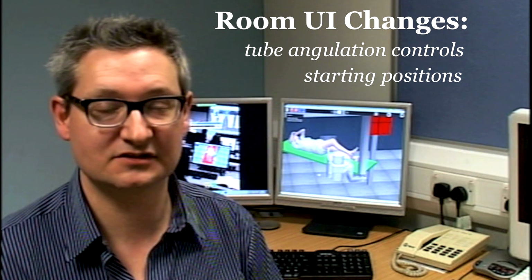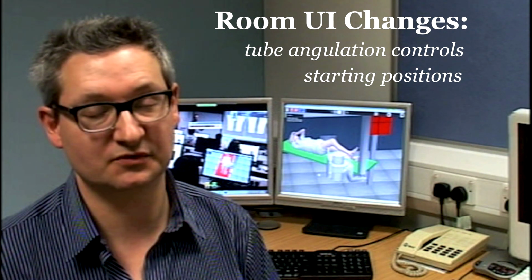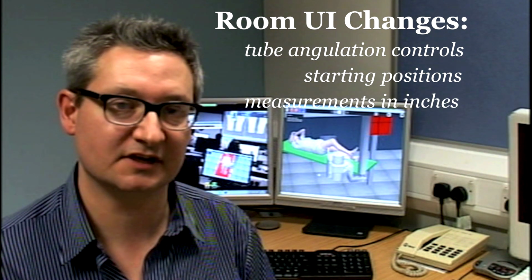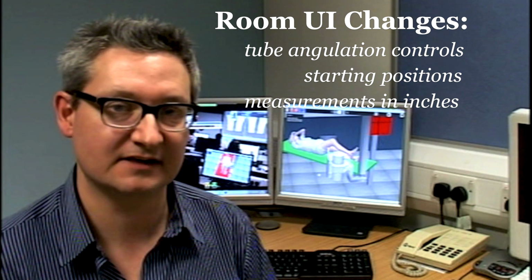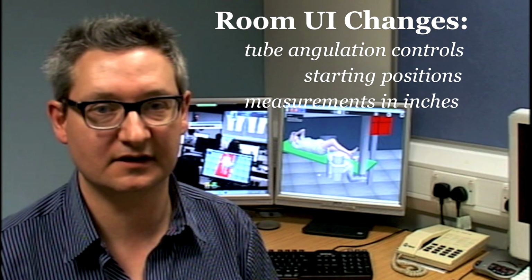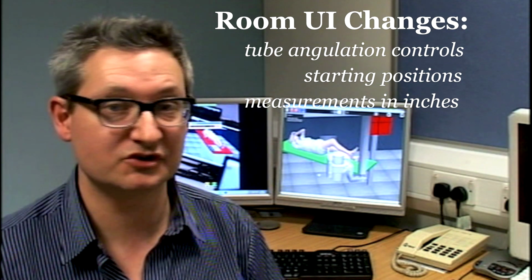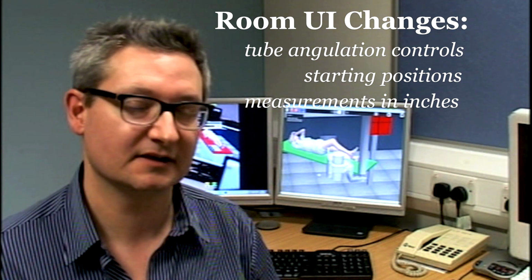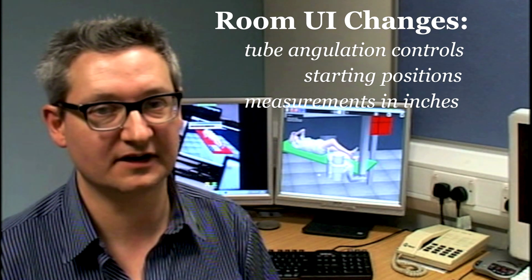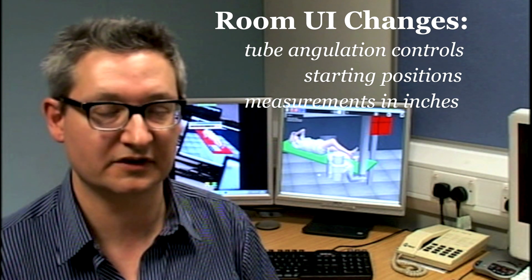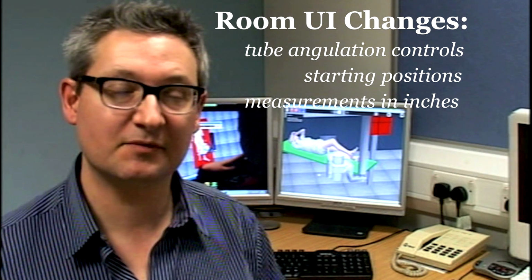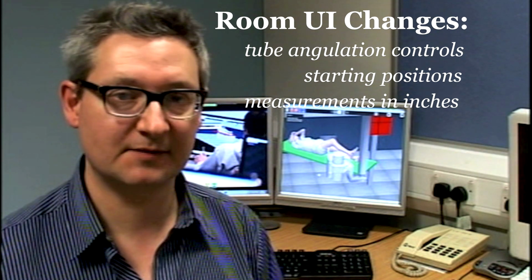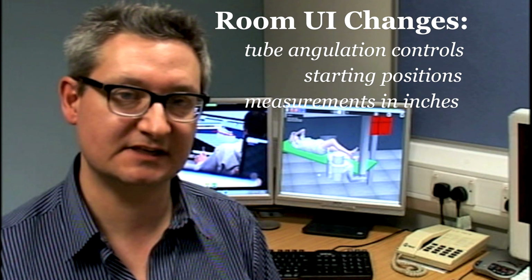They were asking us to display collimation in inches, which we've done, and we've also tidied up some of the source image distances so that their exact inch equivalents are correct instead of the centimetre equivalents. And that will just work if you're in the US. And you can change it and configure it in other parts of the world to work that way if you want.